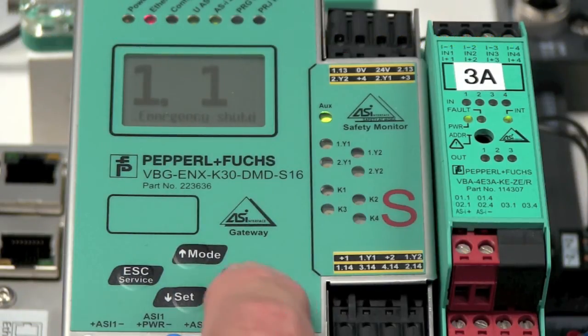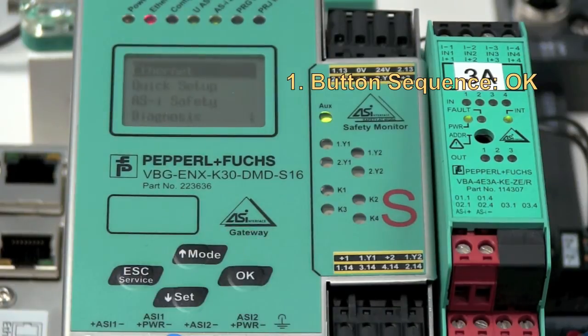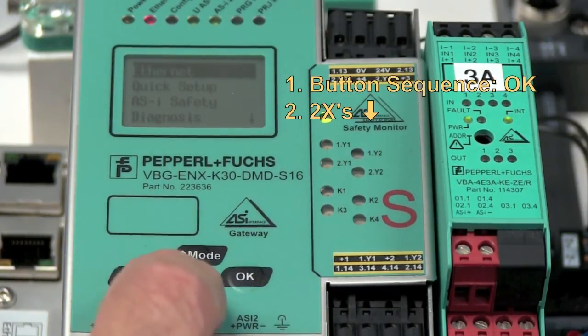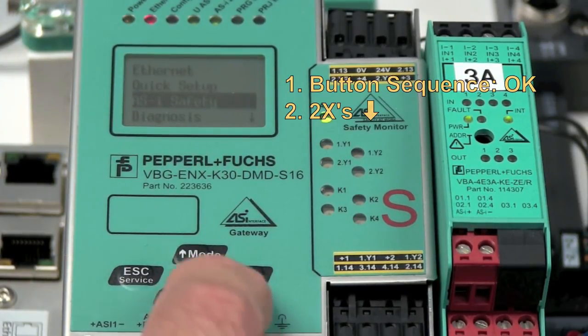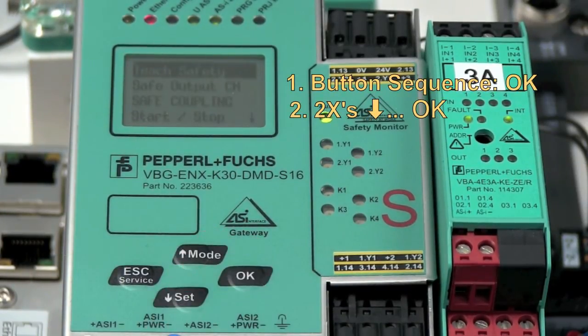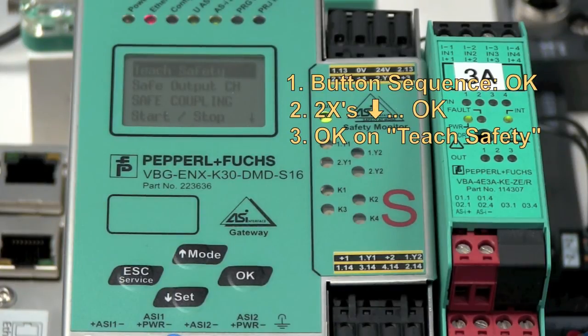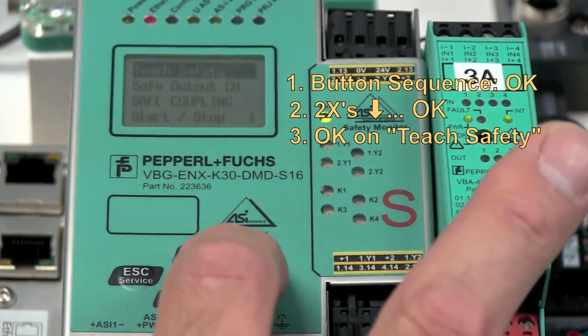We have to correct that. We press the OK button to pull up the menu, tab down for AS interface safety, hit OK, and then select the teach safety option.